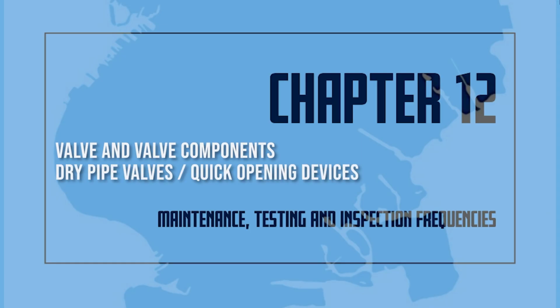Dry pipe valves/quick opening devices. The valve enclosure heating equipment is subject to freezing and shall be inspected daily during cold weather for its ability to maintain a minimum temperature of at least 40 degrees Fahrenheit. Valve enclosures equipped with low temperature alarms shall be inspected weekly during cold weather. Exterior dry pipe valves shall be externally inspected monthly to ensure that they are free from physical damage, the intermediate chamber is not leaking, all trim valves are in the appropriate open or closed position, and electrical components are in service. The interior of the dry pipe valve shall be inspected annually when the trip test is conducted.